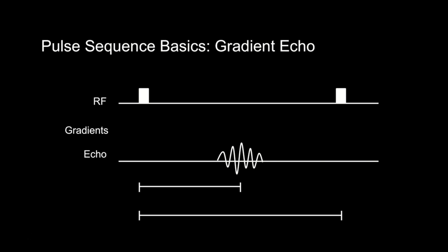We now have enough information to define two key pulse sequence parameters: TE, or time to echo, and TR, or time to repetition, both measured in milliseconds. The TE is defined as the time from the center of the RF pulse to the center of the echo. The TR is the repetition time, defined as the length of time between corresponding consecutive points on a repeating series — more simply, from RF pulse to RF pulse.